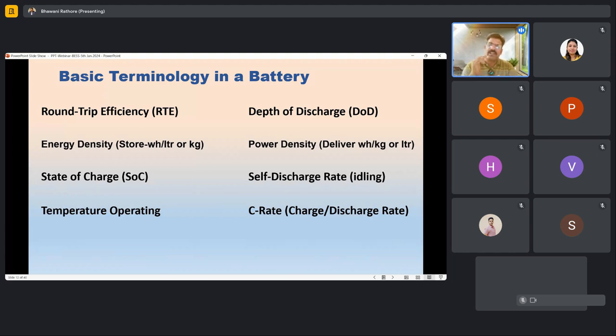Meaning if 0.5C is the given C rate for a battery, for example for 100 ampere hour, 0.5C means if I give 50 ampere for 2 hours, then the battery will be fully charged. But if I give 100 ampere for 1 hour instead, I am not following the given C rate, meaning I am doing fast charging and fast discharging, going against the given rating. So battery life also depends on the C rate, on how we are charging and discharging, and this is seen from its full capacity.